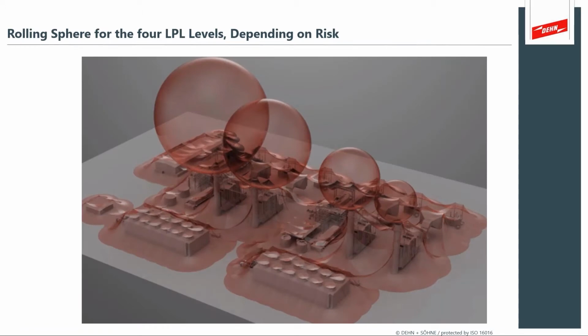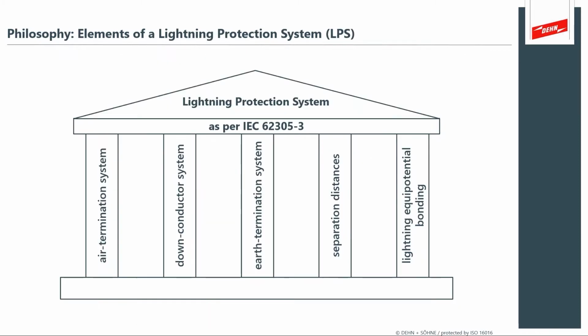Here we see a power generation facility with all those complicated cooling towers, the combustion stacks, the heat exchange, and the electric switch yard where the transformers are going to be located, of course. What we see illustrated is that the smaller sphere is associated with the LPL 1, and a larger sphere is associated with a less stringent LPL 4. So depending on your risk, you will select the lightning protection level, and that will lead you to the selection of that sphere. And then you can design the air terminal placement. What we have illustrated here is that theoretical coverage model that shows you that all of the structures underneath the air terminals are protected. And depending on the rolling sphere that you use, you can generate a coverage that is sufficient for that power generation facility.